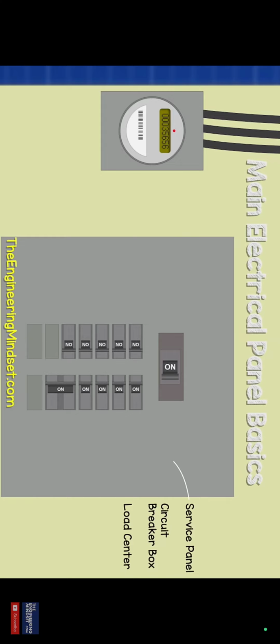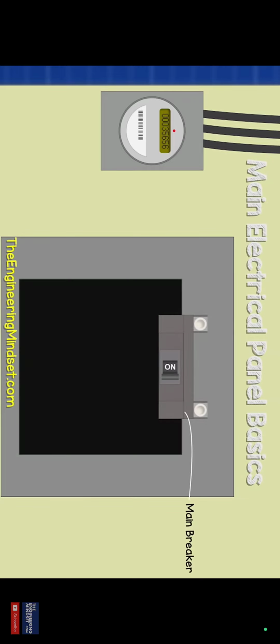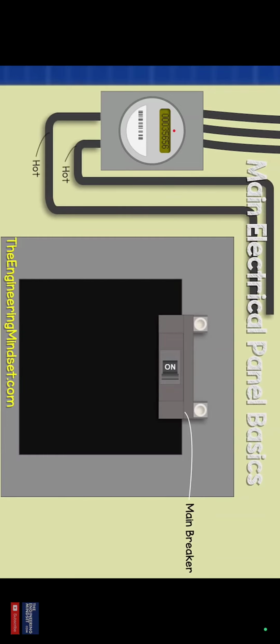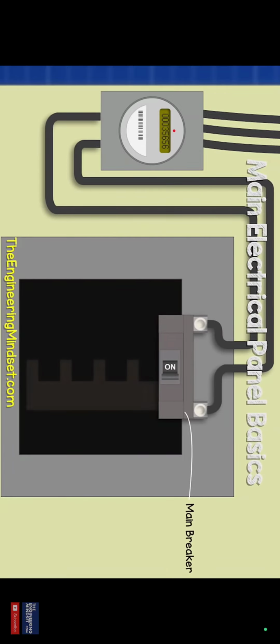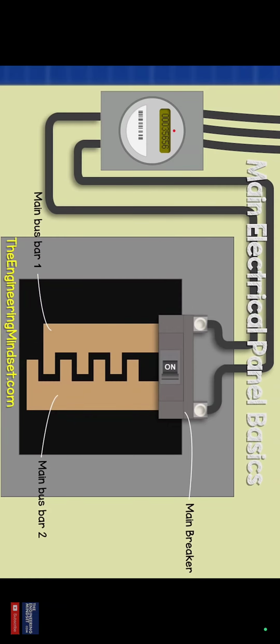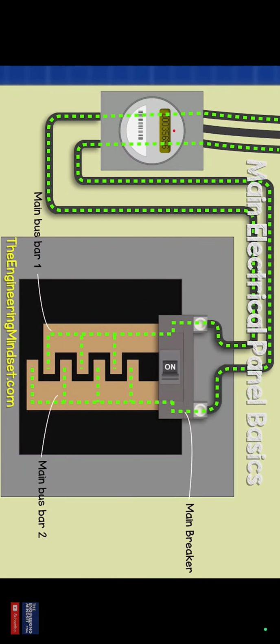So if we zoom into the property, we find a main service panel, which is sometimes called a load center or breaker box. If we remove the cover and look inside, we first find the main breaker. This is usually at the top of the panel, but it might be at the bottom. The two hot wires from the electricity meter will connect directly to the lugs on the main breaker. Coming out of the main breaker will be two main bus bars. These are basically exposed metal sheets which carry electricity to the circuit breakers.